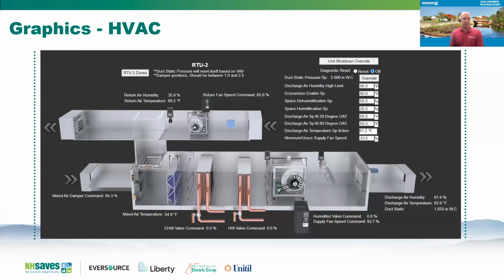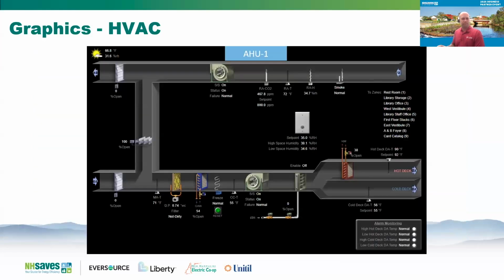As opposed to a very modern graphic here where you've got animation. So if that fan is on, you'll see the fan spinning, as well as lots more information being provided. You're getting a lot more points. You're getting different sequences shown oftentimes. So you can see here there's a discharge air set point at 20 degrees outside air and 60-degree outside air. So that tells you they've got a supply air reset schedule, perhaps. It may not actually work, but it visually shows here that there's a good chance that they have a supply air or discharge air reset sequence. So these graphics can be very helpful for diagnosing what opportunities are available.